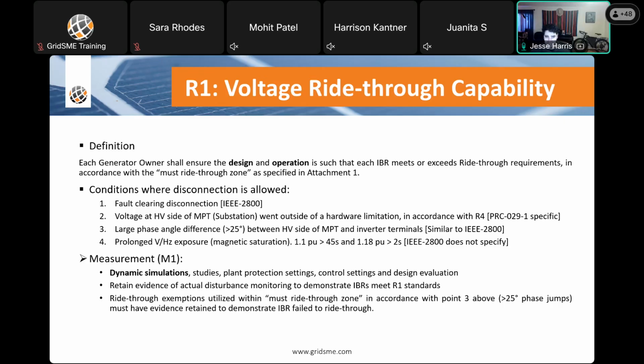And number 3, large phase angle difference between the high voltage side of the MPT and the inverter terminals. This one's quite technical, but essentially non-fault switching events can cause sudden jumps in phase angle, which can disrupt the logic within the inverter. And what NERC is saying here is that stability and control integrity has greater priority than fault ride-through. And then number 4, prolonged volts over frequency exposure. This essentially causes magnetic saturation, which can damage equipment like the main power transformer and other very expensive equipment on the bulk power system.